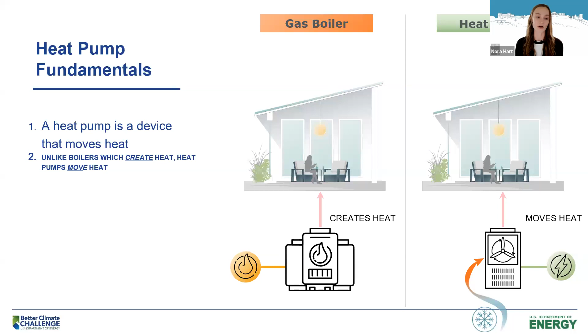Why heat pumps? Why are we so focused on this for electrification? Mainly because heat pumps are highly efficient. Natural gas combustion converts one type of energy into another, which results in some losses and has a max efficiency of 96%. Heat pumps aren't converting from one form of energy into another; they're instead moving heat from one place to another using the refrigeration cycle. This makes them a lot more efficient, up to 500% efficient compared to boilers, meaning for every 1 unit of electricity used, they can create 4 or 5 units of heat.